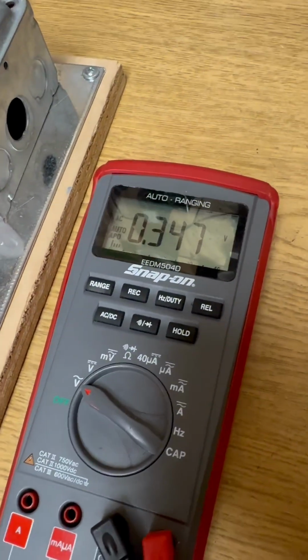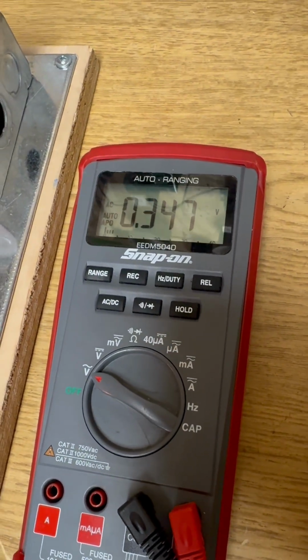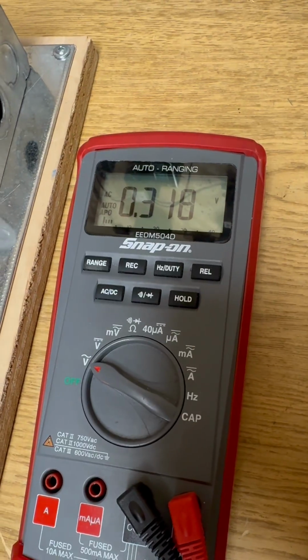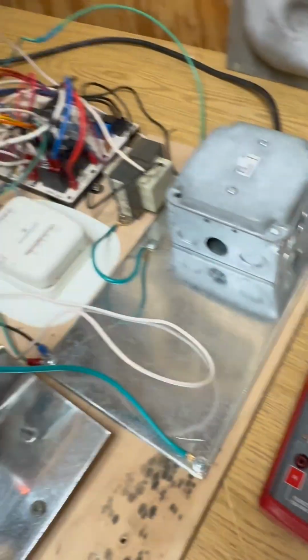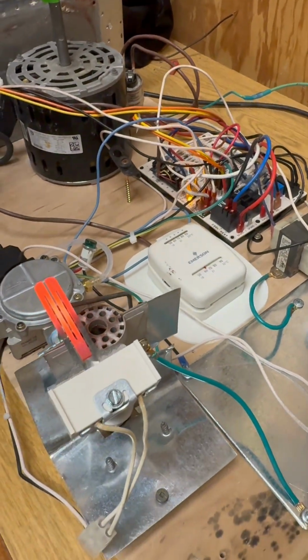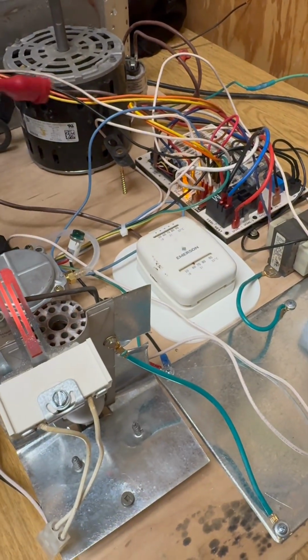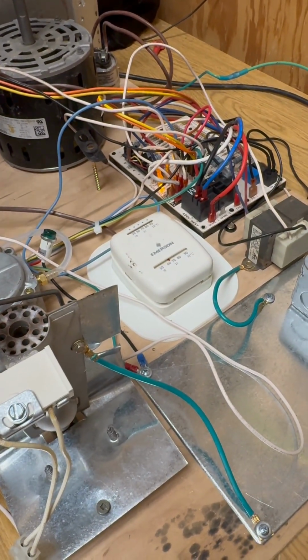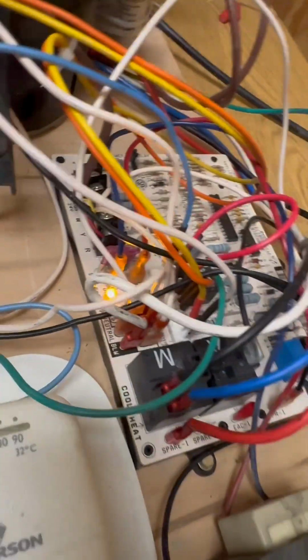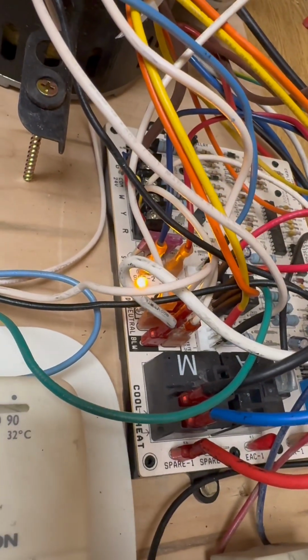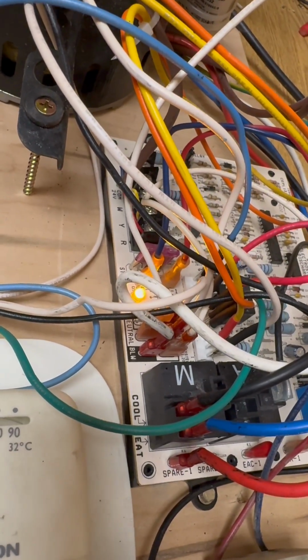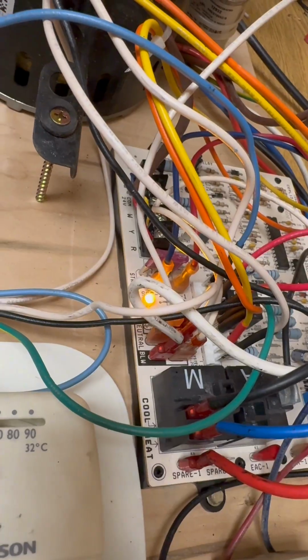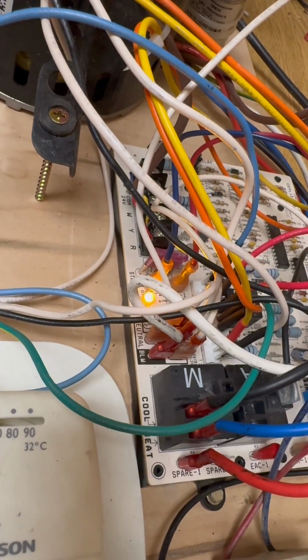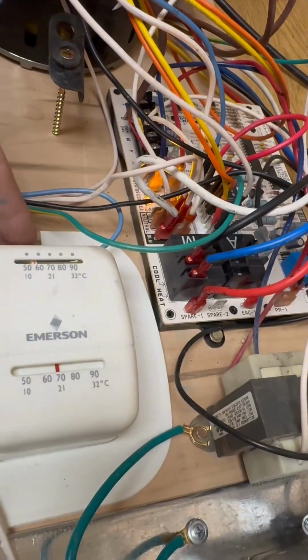So you hear the click from our furnace board, and we're not getting any voltage. So that shows our gas valve isn't getting any power. So we're going to turn our thermostat off. We're going to check to see if we get any codes, which it should give us a code since our gas valve isn't working, which it is not. So let's try this again.